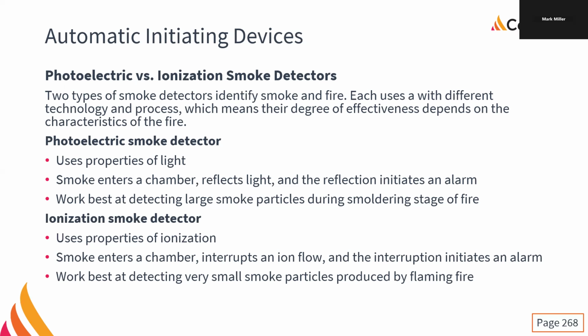Ionization smoke detectors use the properties of ionization. The smoke enters the chamber, it interrupts an ion flow, and that interruption initiates the alarm. They work best at detecting very small smoke particles. The big black smoke that you see when you're starting a campfire and stuff like that can't be detected by an ionization smoke detector. Those particles are too big. We actually have to filter out those big particles. We're only looking for the small stuff. So they're great at very small smoke particles produced in the incipient stage, which is the first stage of fire, and the flame stage, the third stage. They don't work well in the second stage.